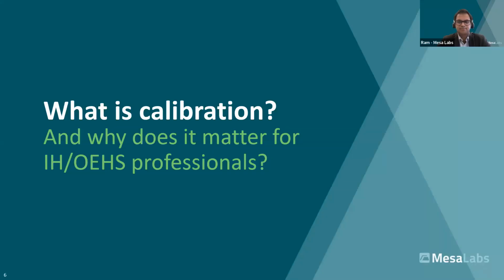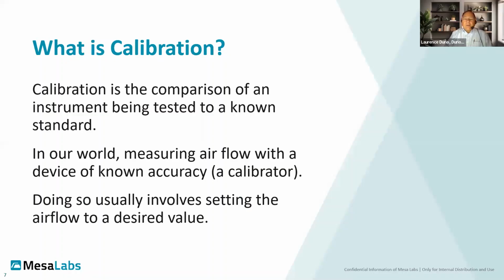Okay, first, what is calibration? It is comparison of an instrument to a known standard, the emphasis being known. Normally for industrial hygiene purposes, at least within the context of this webinar, we're talking about airflow, though the general principles apply to acoustics and radiation, other physical agents. We measure the flow with a known accuracy device, which we call a calibrator. Typically, we don't just stop with measuring the flow, we will adjust it to a known desired value for various reasons, some of which are operability of our equipment, some are simply our convenience.